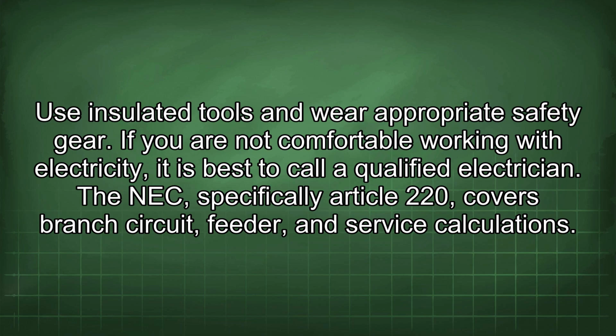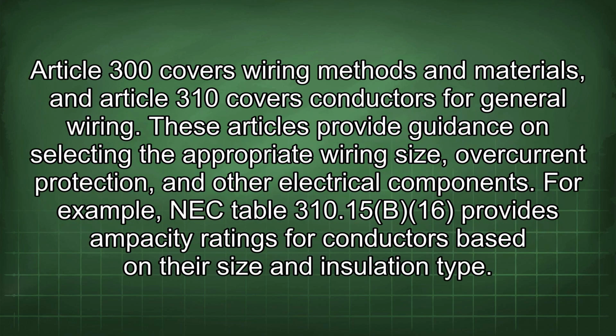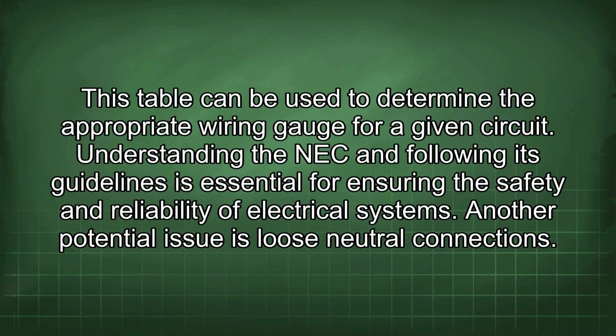The NEC, specifically Article 220, covers branch circuit, feeder, and service calculations. Article 300 covers wiring methods and materials, and Article 310 covers conductors for general wiring. These articles provide guidance on selecting the appropriate wiring size, overcurrent protection, and other electrical components. For example, NEC Table 310.15(B)(16) provides ampacity ratings for conductors based on their size and insulation type. This table can be used to determine the appropriate wiring gauge for a given circuit. Understanding the NEC and following its guidelines is essential for ensuring the safety and reliability of electrical systems.